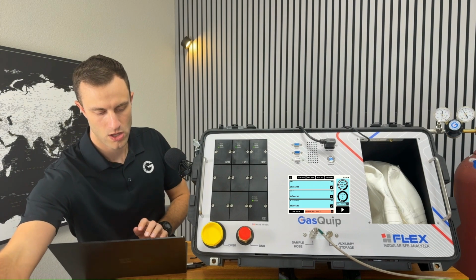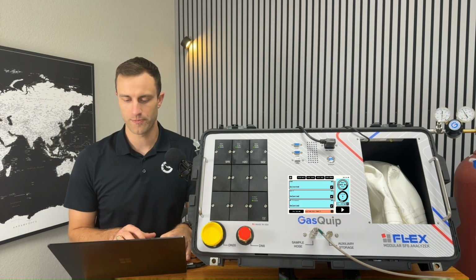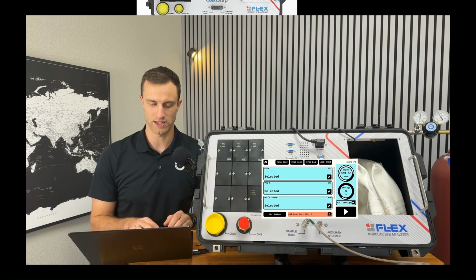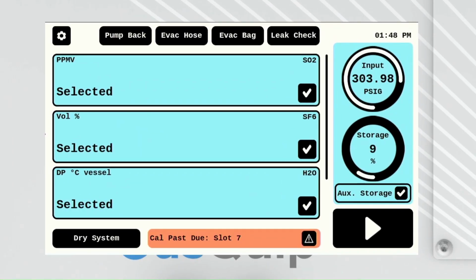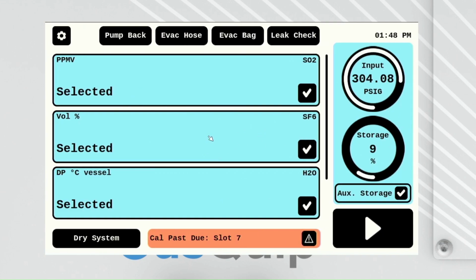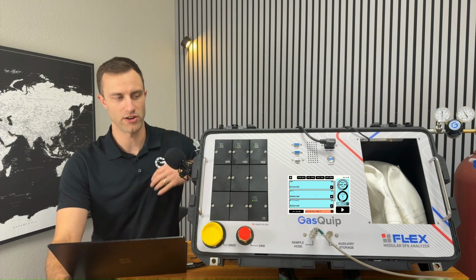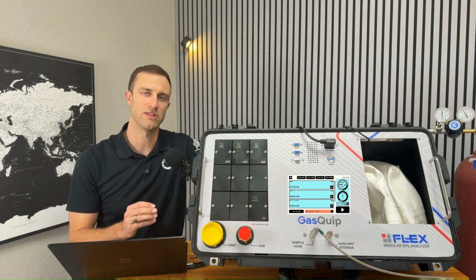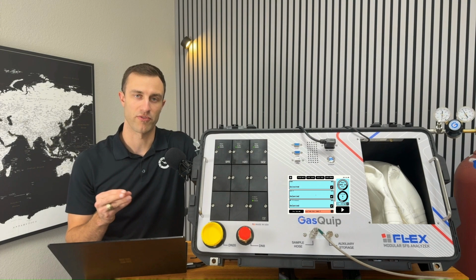Now, the fourth way would be to do a leak check on the system itself. So if we go back to the analyzer close-up, we can run a leak check. Again, that's going to pull a vacuum on all of our modules and our module manifold here, and then check to see that those are holding a proper vacuum.